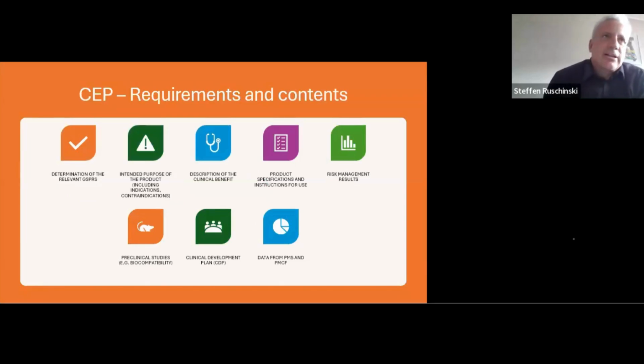Before we can write a clinical evaluation report, we have to plan this report: what are the requirements and what are the contents of the CEP. We have to determine the relevant GSPRs. We have to set the intended purpose of the product, including indications and contraindications. We have to describe the clinical benefit, the product specifications and instructions for use. We have to include the risk management results already, preclinical studies, for example biocompatibility. We have to include a clinical development plan for this special product and our data from PMS and PMCF.